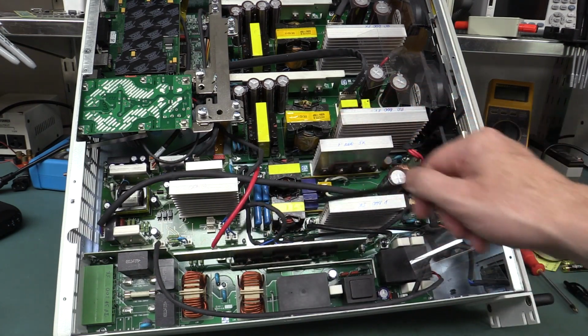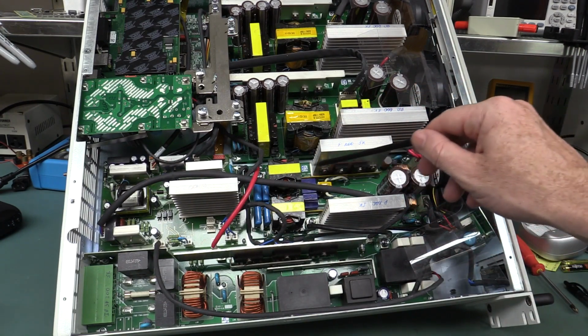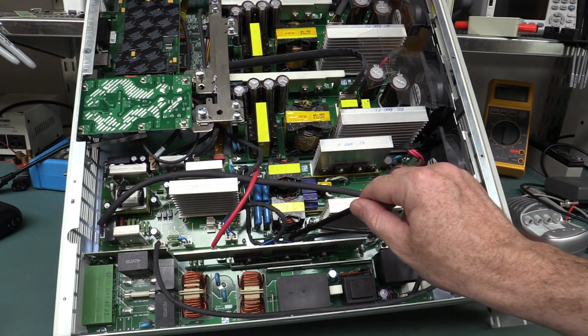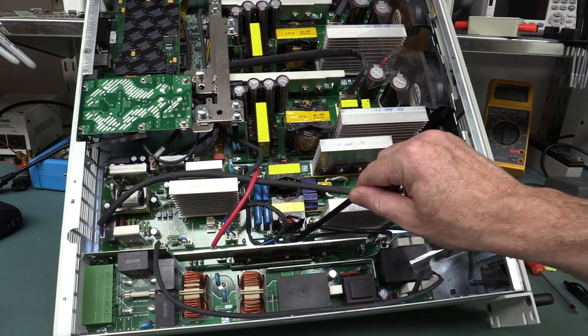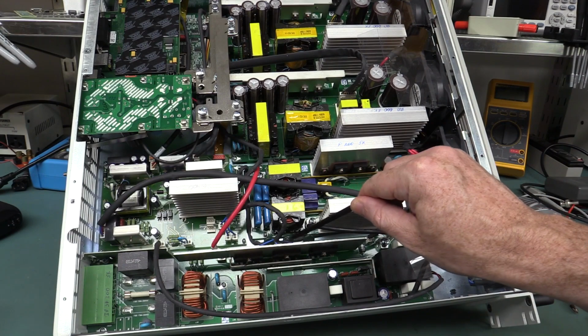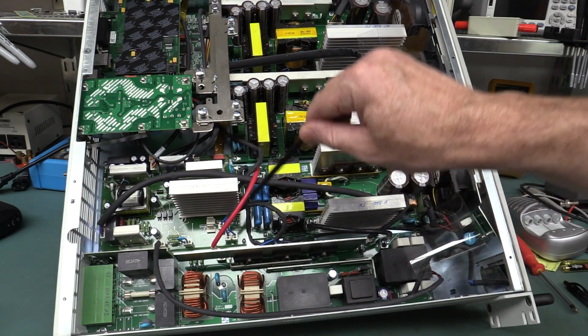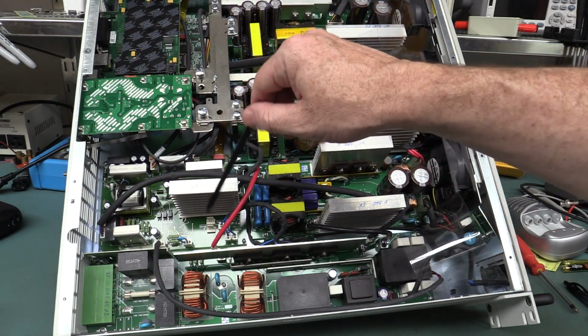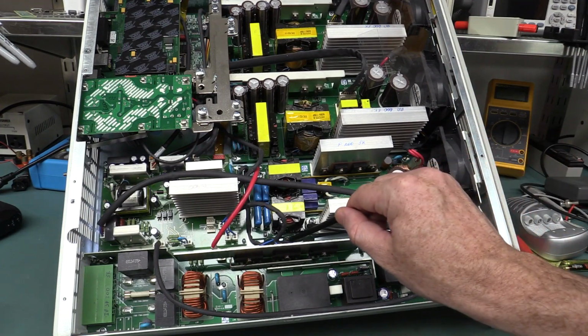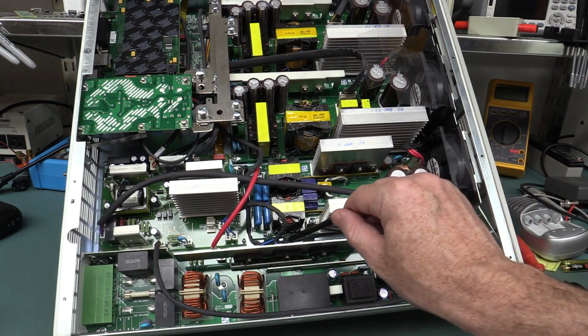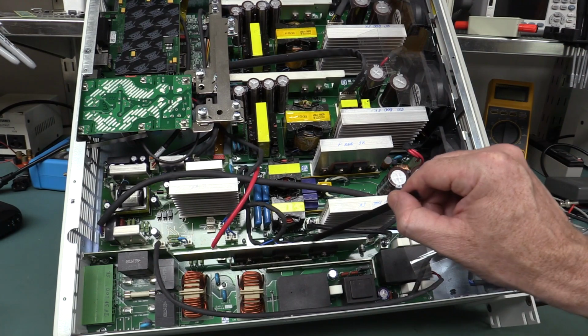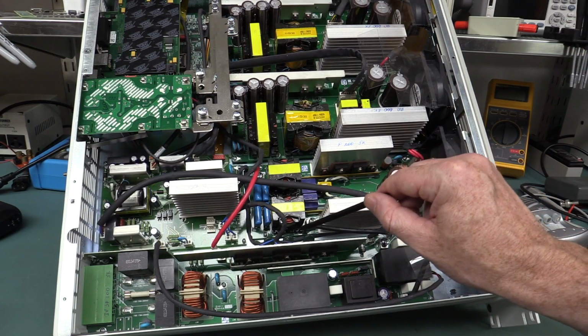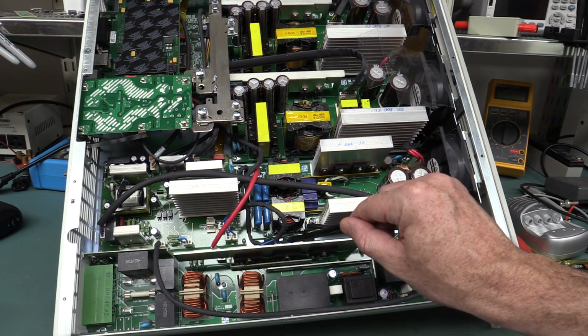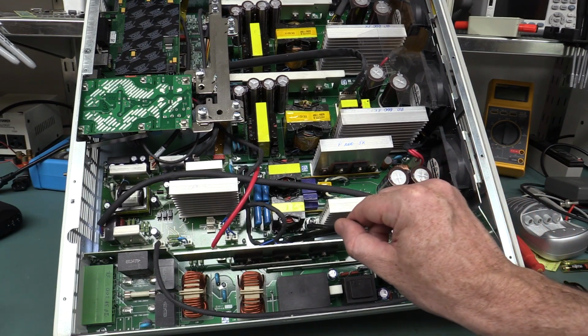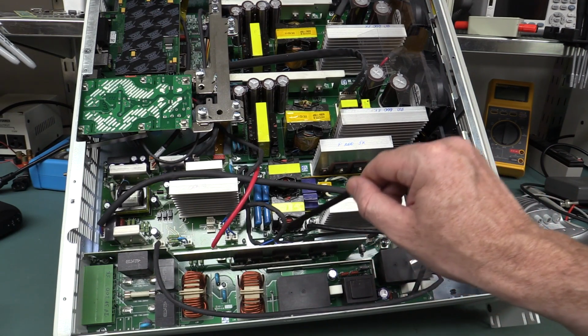It's going to jump over to this power factor correction circuit, and like we've got a little MOV down here which is blowing on this side, but it's only for the low energy stuff going over to this secondary one. So that's not like a main MOV, I don't think, from what it looks like. Might have to get the board out to check the wiring. It doesn't look like it's directly in the path, but it's still there and it blew.